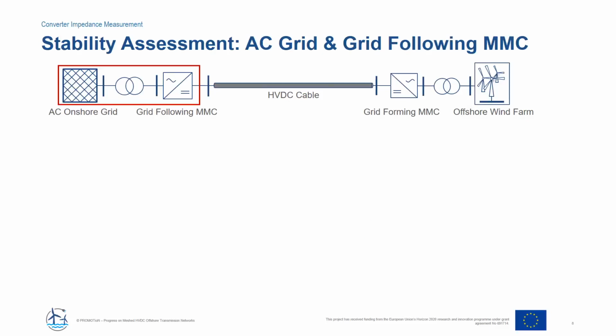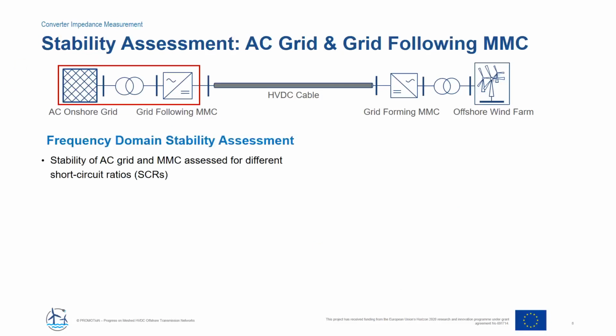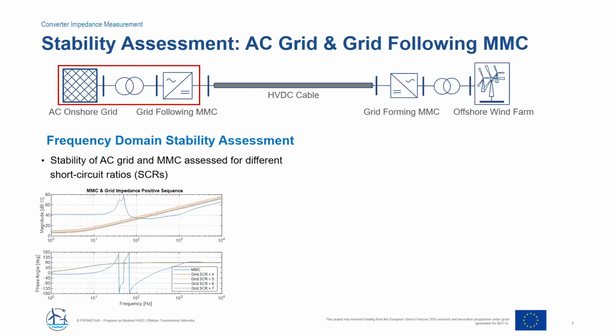In this slide, we show the assessment with the AC grid and grid following MMC, as circled by the red squares. We vary the grid strength of the AC grid, the so-called short circuit ratio, and as you can see here, the blue curve is the MMC's frequency impedance, and there are a few different colors showing the grid impedance representing different short circuit ratios.